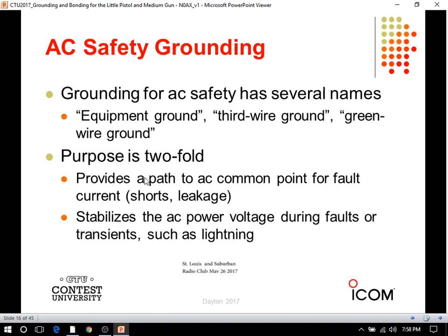It doesn't know about your RF. It doesn't care about your RF. Its job is to provide a path back to this AC common point, usually in your circuit breaker box at your home, for fault currents, either from short circuits inside a piece of equipment or for leakage current. Sometimes insulation breaks down, and you want those currents to go back to a safe point, not through you.